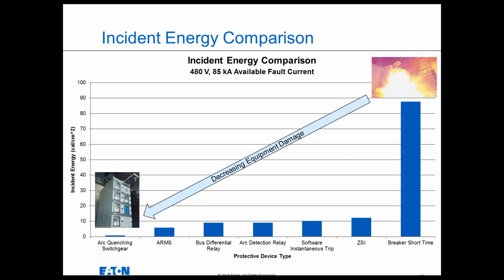So in terms of incident energy, I use the old IEEE 1584-2002 method here just for simplicity, and compared a number of different ways of clearing a fault at 480 volts and 85 kA available fault current. On the right-hand side, if the main breaker held in for a full 30 cycles, the incident energy would be nearly 90 calories per centimeter squared, and that is exactly what the equipment would look like.